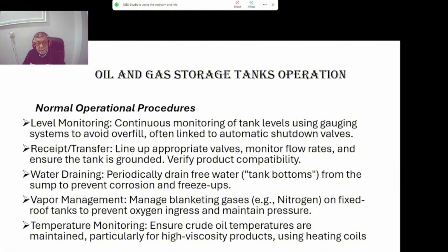Vapor management: manage blanketing gases, nitrogen, for fixed roof tanks to prevent oxygen ingress and maintain pressure. Blanketing gas is only for fixed roof tanks. Fixed roof tanks are only used for heavy oil if it is not volatile. But for volatile product we use floating roof tanks, so no blanketing gases are needed, only because the roof is movable. Temperature monitoring: ensure crude oil temperature is maintained, particularly for high viscosity product, using a heating coil. If the viscosity is high, we use a heating coil inside the tank.